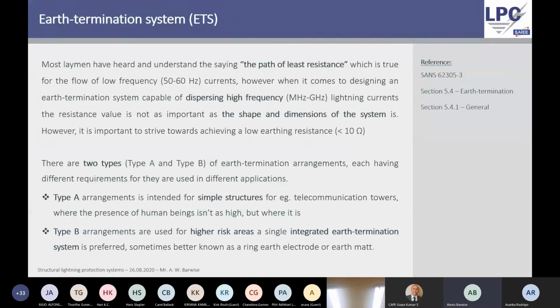Here we read from the standard that the shape and the dimensions of the earthing system are the key factors. It says that it's important, so we strive towards a path of low resistance, the 10 ohm value we also know, but it's not the critical item. The critical items under high frequency behavior for the earthing system is how we have shaped it, so where it is lying, and the dimensions, so the size of the conductors itself. The standard gives us two types of arrangements. The first is type A, which is where we are using for simple structures, maybe a simple home as an example, or a small telecommunication tower. It is where we have either a single vertically driven into the ground electrode, or we have a trench that we have made and we have a single horizontal conductor.